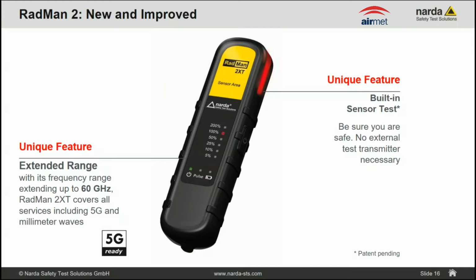Excessive radiation means above the destruction limit, which is well described in the data sheet. So if you are in fields above the destruction limit, there is a risk that the diodes burn because of too high signals. Be aware that this is also possible if the instrument is not switched on - it has nothing to do with whether the instrument is switched on or off.